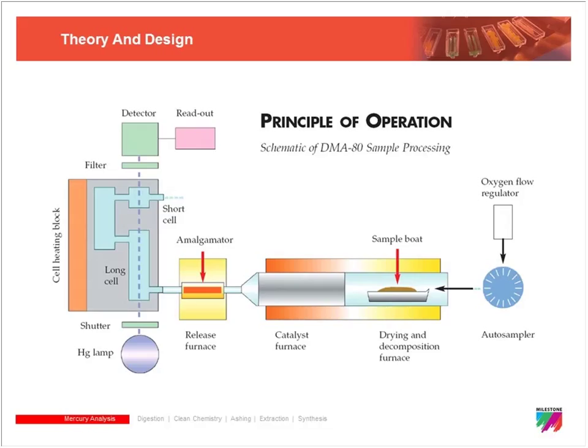So here's a schematic on exactly how our system works. Starting from right to left, we use a carrier gas. So you can see from the oxygen flow regulator, you can use oxygen or compressed air. Your samples are loaded onto the 40-position auto sampler tray, where they are carried into the decomposition furnace. In the decomposition furnace, the sample is completely combusted, volatilizing any mercury that is contained within the sample. The carrier gas then moves the mercury and all of your other sample contaminants into the catalyst. And the catalyst is the heart of the system here. There's two functions that the catalyst has, the first being to trap any non-mercury contaminants from passing into the spectrophotometer cell, but it also reduces all the mercury species to elemental mercury, Hg0.